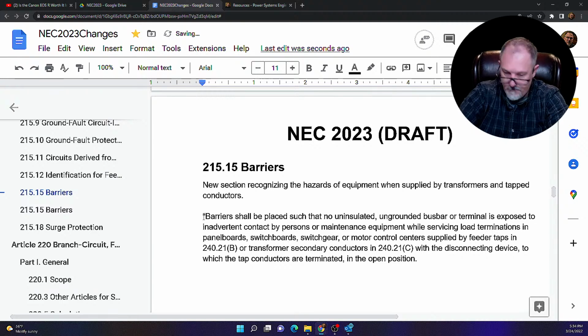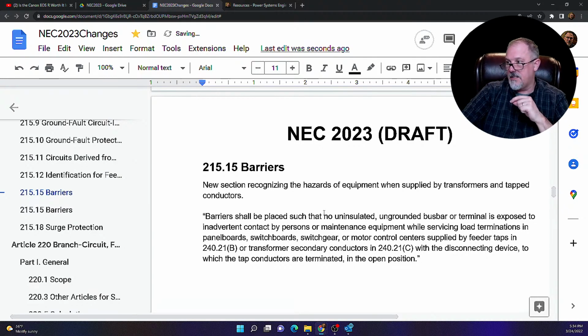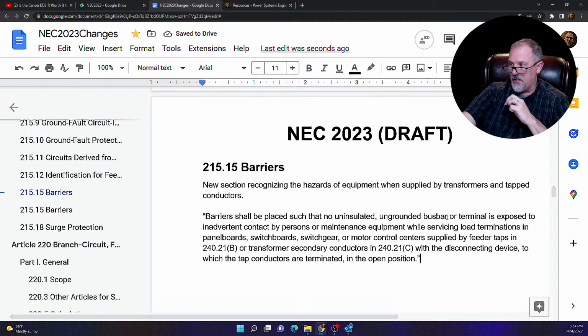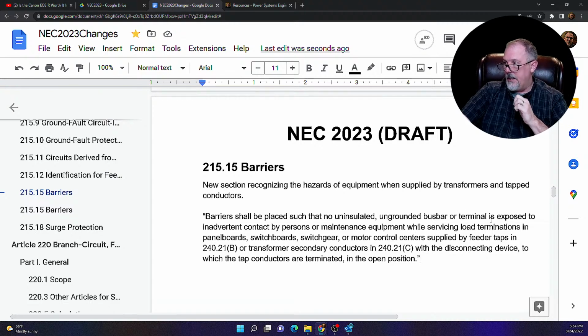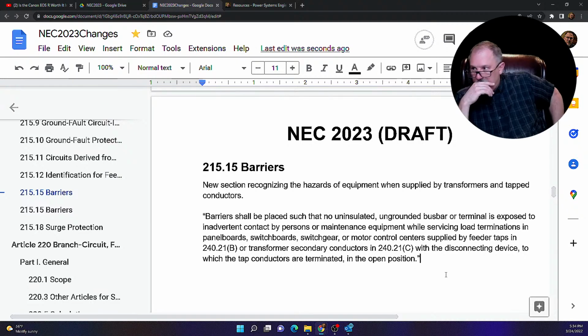Barriers shall be placed such that no uninsulated, ungrounded bus bar or terminal is exposed to inadvertent contact by persons or maintenance equipment while servicing load terminations in panel board, switchboard, switchgear, or motor control centers supplied by feeder taps in 240.21b or transformer secondary conductors in C when the disconnecting device to which the tap conductors are terminated in the open position.